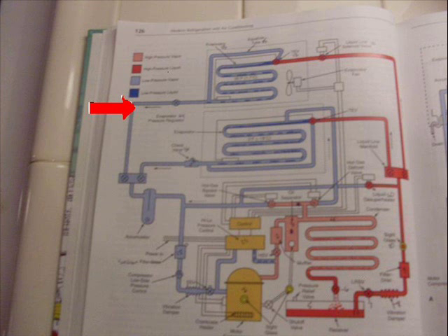The evaporator pressure regulator, its job is to maintain and force a higher pressure in that evaporator to drive the temperature up. That EPR valve is what creates the second temperature so we can operate two different systems with two different temperatures. Without the EPR valve, we'd have two coils at the exact same temperature. We don't want that. The EPR valve is a pressure regulator and backs refrigerant pressure up until the pressure goes over a predetermined spring range. That's it. EPR valves are field adjustable. There's a spring you can crank down on them. Maintains a back pressure to maintain a higher temperature.